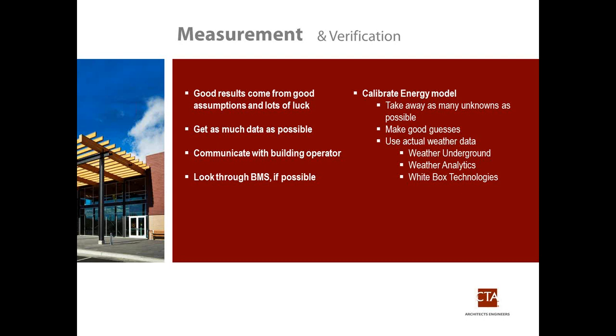When you're modeling and doing measurement verification, try to get as much data as possible. Talk to the building owner, see how they're using the building, how many people are in there, how many computers. The more information, the better. It may make it harder to calibrate the energy model, but it's going to be a more accurate model in the end.